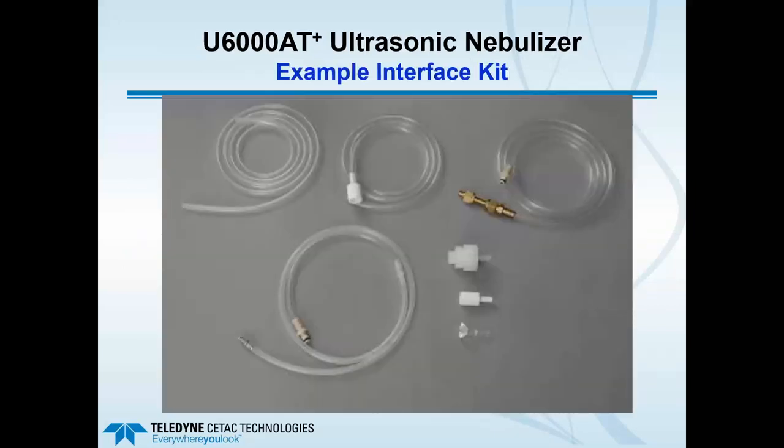Every unit, whether a U5000 or U6000, is shipped with an interface kit, which allows you to connect an argon gas supply to the ultrasonic nebulizer and the outlet to the host ICP torch. We have these kits for all the major manufacturers.